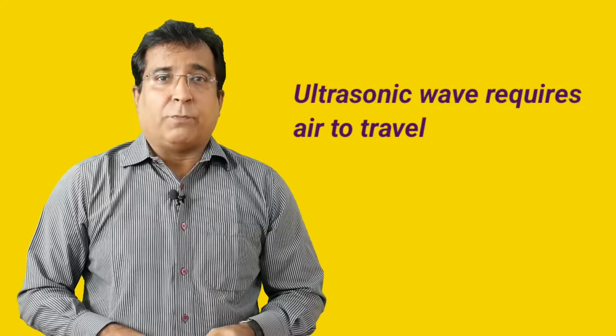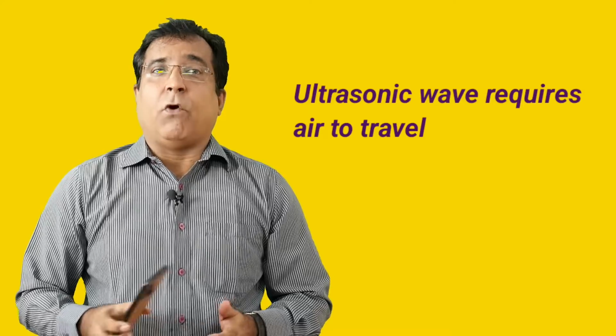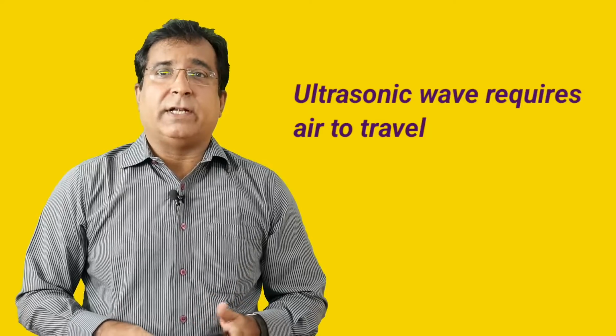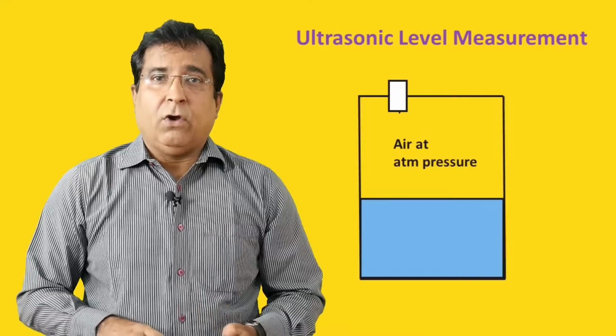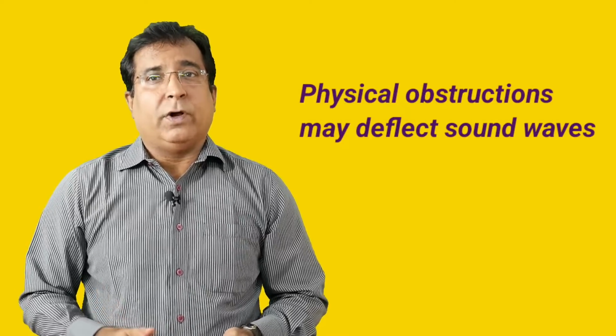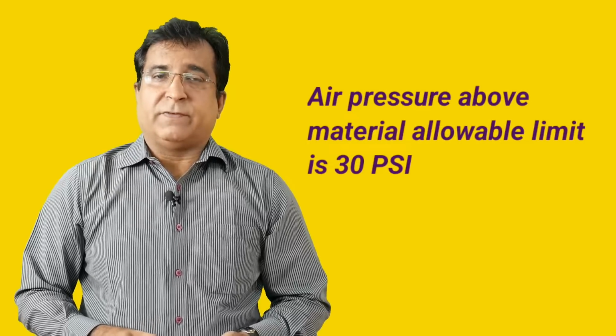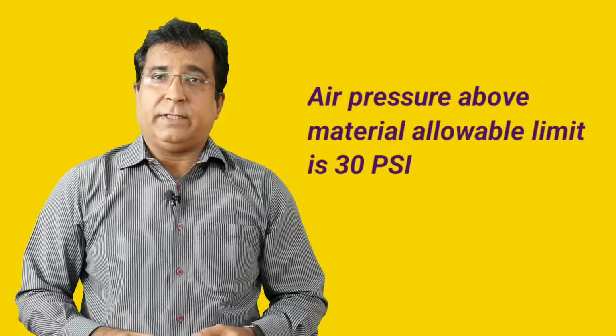Now, an ultrasonic sensor requires an unblocked air column for the sound waves to travel to the material, because sound needs air to travel. Obstructions like a mechanical agitator, excessive foam, heavy vapors, thick dust, and light powders above the material can deflect or absorb the sound waves, or simply act as a false surface, leading to erroneous readings. This air above the material is expected to be at atmospheric pressure, or must not exceed 30 psi. So we saw the ultrasonic sensor works best when an air column is present above the material to be measured.